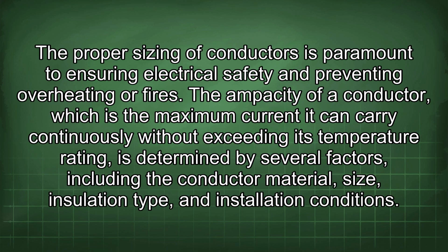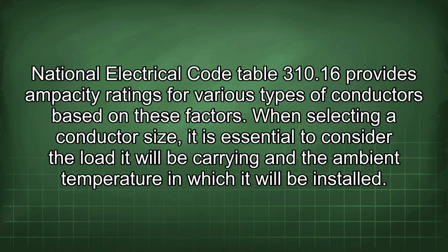The proper sizing of conductors is paramount to ensuring electrical safety and preventing overheating or fires. The ampacity of a conductor, which is the maximum current it can carry continuously without exceeding its temperature rating, is determined by several factors, including the conductor material, size, insulation type, and installation conditions. National Electrical Code Table 310.16 provides ampacity ratings for various types of conductors based on these factors. When selecting a conductor size, it is essential to consider the load it will be carrying and the ambient temperature in which it will be installed.